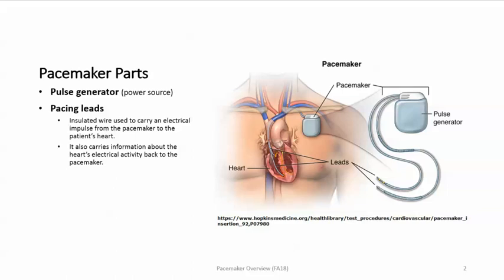Pacemaker parts. The pacemaker system consists of a pulse generator, which is the power source, and pacing leads. These are insulated wires used to carry an electrical impulse from the pacemaker to the patient's heart. The leads also carry information about the heart's electrical activity back to the pacemaker.